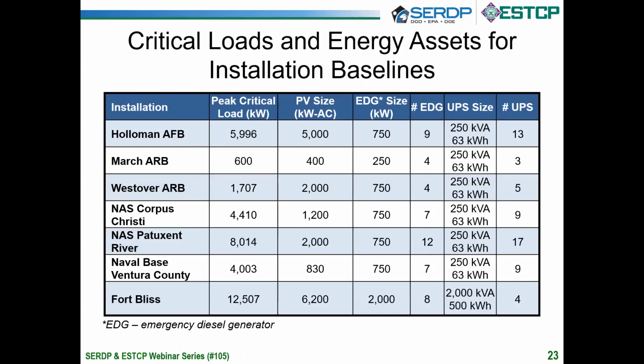To make sure we could meet ride-through capability, i.e. the portion of the load which cannot afford any even momentary interruption in its power, we also assigned a number of standard UPSs whose sizes and numbers are listed on this chart. So this defines what the baseline microgrid diesel-only generator system is. And I want to talk now about how we went about calculating the reliability performance and what those metrics actually look like. Slide 24.